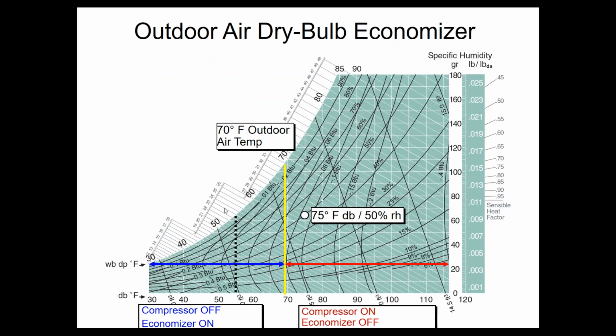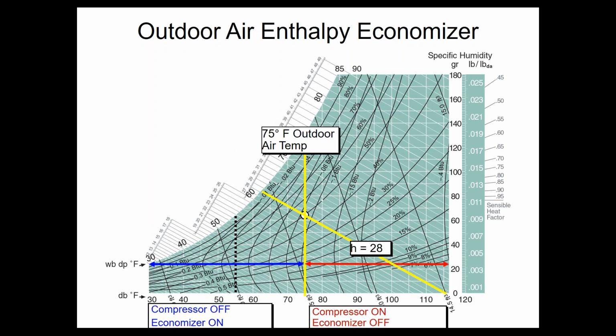If I was to graph those out, that little black line is my old 55 degree set point on my psychrometric chart. Now I move all the way over to the yellow line. So it's a lot more days that I'm going to need to have an economizer operating, so a lot more energy savings. I'm going to graph the enthalpy out, 28. That's those little tiny numbers off to the left hand side of the chart. I graph down that 28 there. Now, anything below the 28 and to the left of the 75 degree number becomes an economizer day. To the right of that or above that is a non-economizer day.